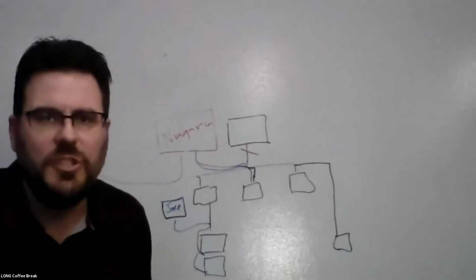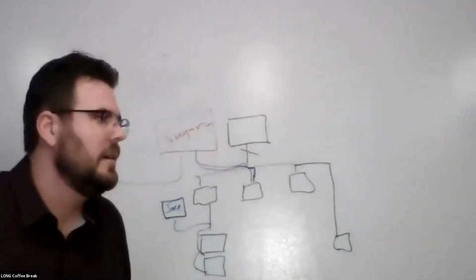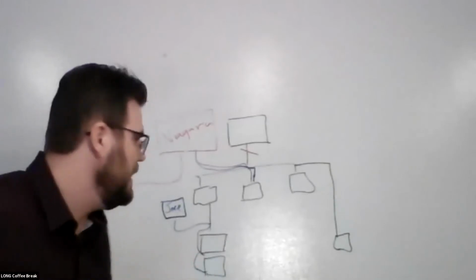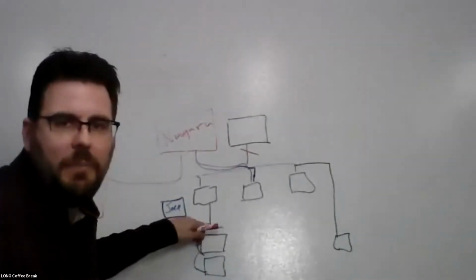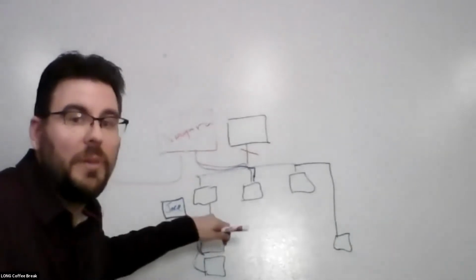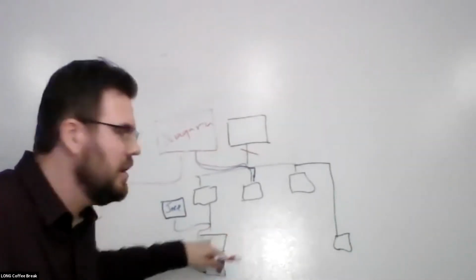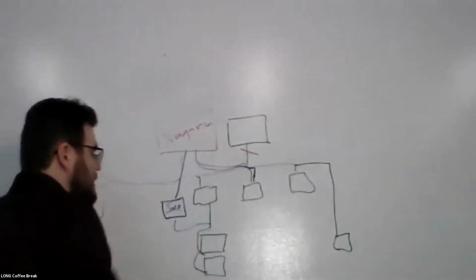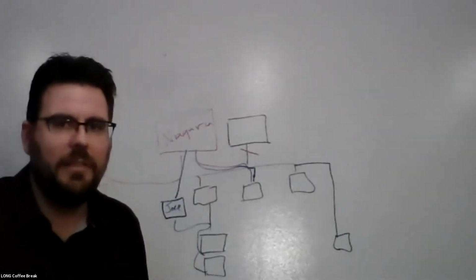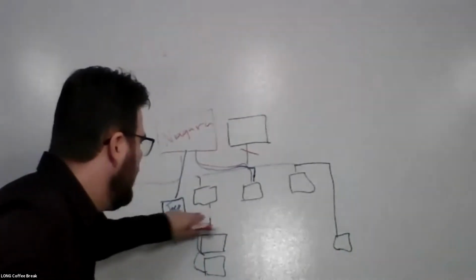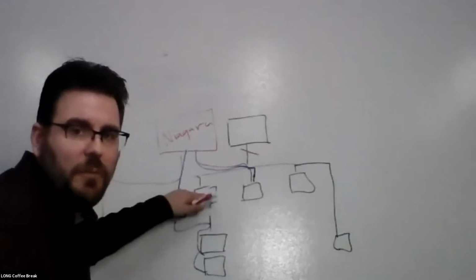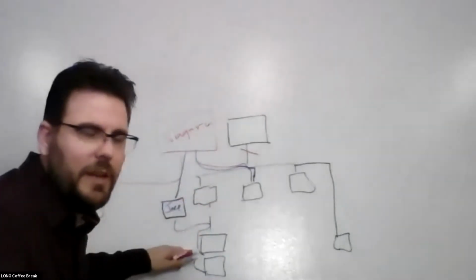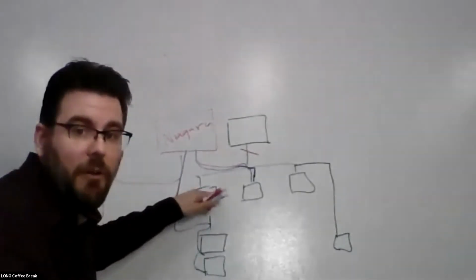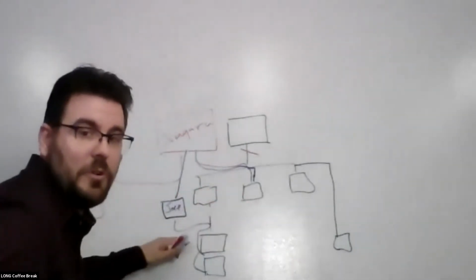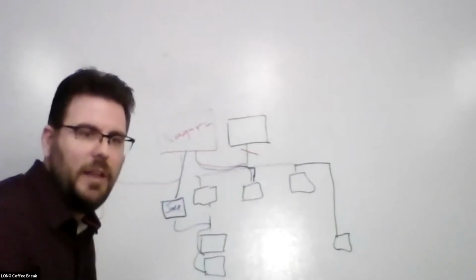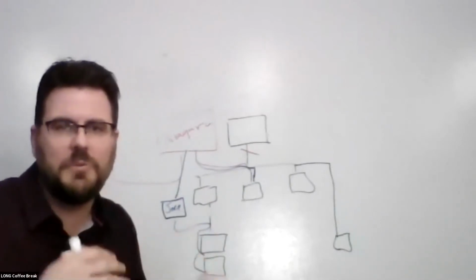That physical Jace is a Niagara product. It's a piece of hardware that now connects in, and we can pick up that proprietary protocol, or we can pick up that MSTP trunk, and then bring that up into Niagara. So it's a path that you can now pluck off and remove this connection from this equipment controller to the field level network, and then start to migrate your equipment level controllers, or start to migrate your field level controllers. It just gives you optionality.